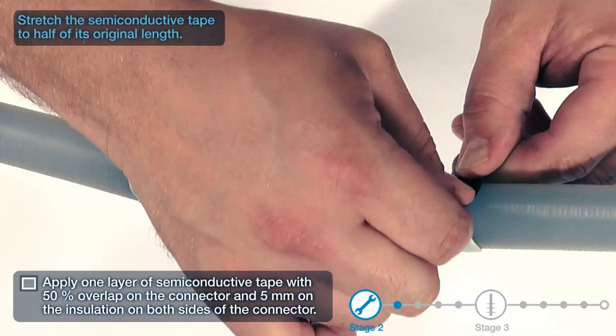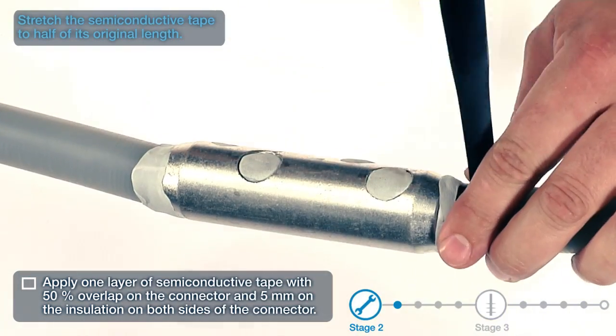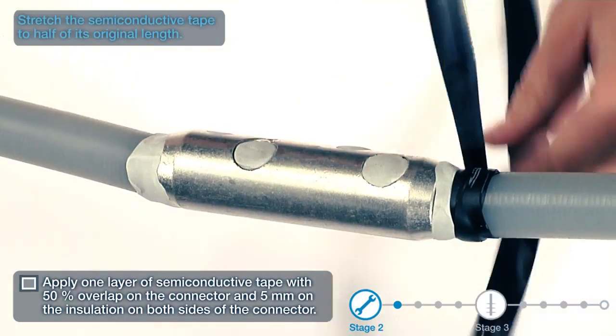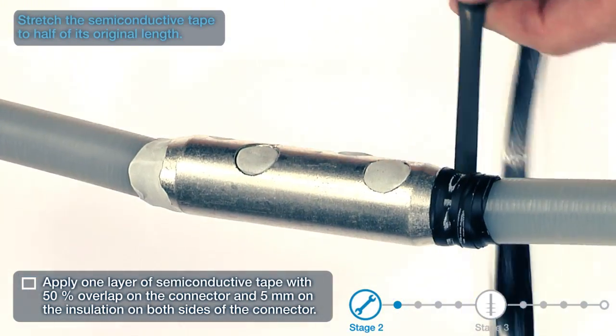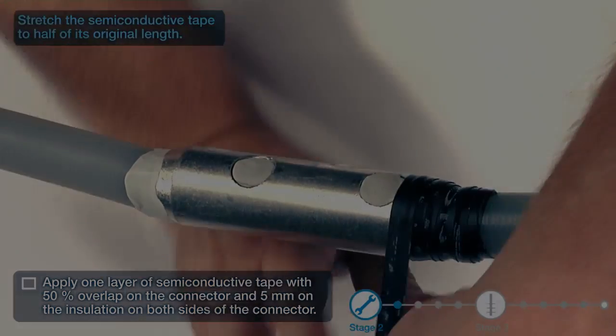Apply one layer of semi-conductive tape with 50% overlap on the connector and 5mm on the insulation on both sides of the connector. Stretch the semi-conductive tape to half its original length.